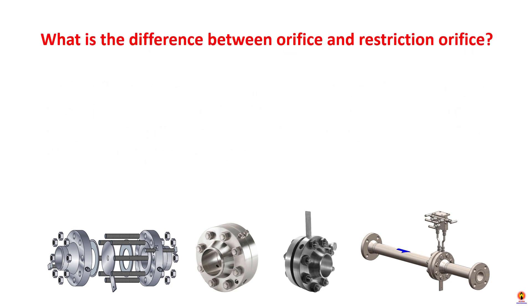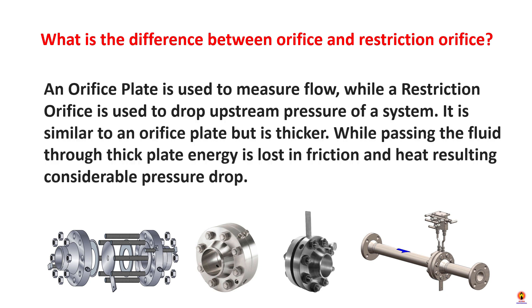What is the difference between an orifice and a restriction orifice? An orifice plate is used to measure flow, while a restriction orifice is used to drop the system pressure. It is similar to an orifice plate but is thicker. While passing fluid through the thick plate, energy is lost in friction and heat, resulting in a considerable pressure drop.